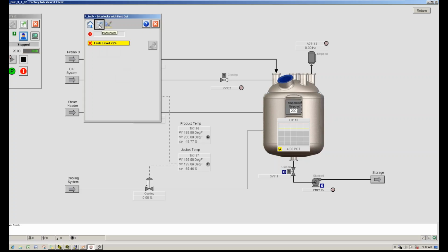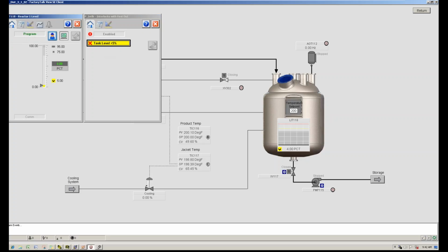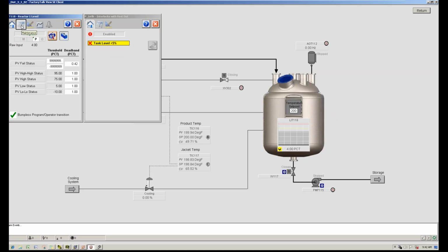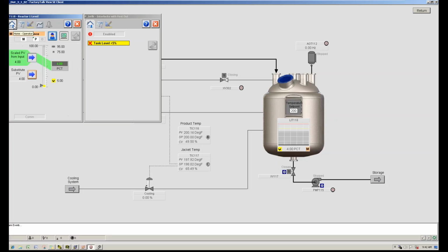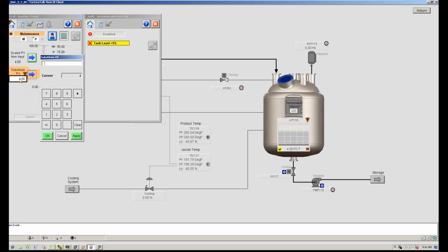But say that we determine that it's actually a faulty transducer on the tank at the moment. If I click on that yellow tank level less than 5%, it takes me to the analog input, the source of this level. If I determine that my field instrument is faulty, and that's why I can't operate the agitator, I can go into this maintenance mode, and this allows me to use a substitute value, and I can say, well, I know my field device is faulty, so that I can run my agitator.